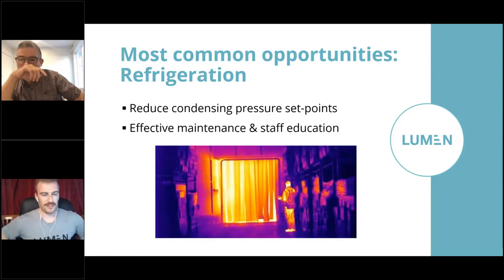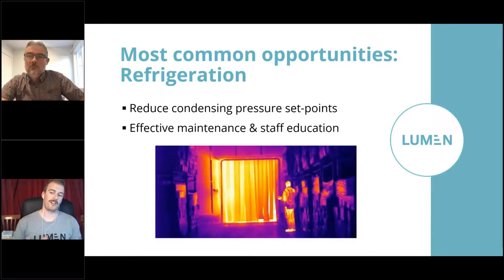Cool. So refrigeration, it's a really complex topic. This is one of those ones you could definitely do a series of webinars on, so we will just be scratching the surface. But in the first opportunity, in a refrigeration system, a compressor is used to compress and heat up a gas. So that can then be used to transfer heat out of the refrigerated space, and that's usually to atmosphere. And often the pressure set point that the compressor is compressing to is a lot higher than what's actually required for the system to run effectively, and it can be reduced. The compressor power requirement is then reduced. You have a little bit of a penalty on your fan power from your cooling towers, but most often the overall result is a significant reduction in power consumption, to the tune of 5-10% sometimes.